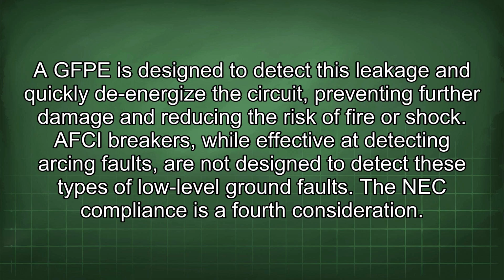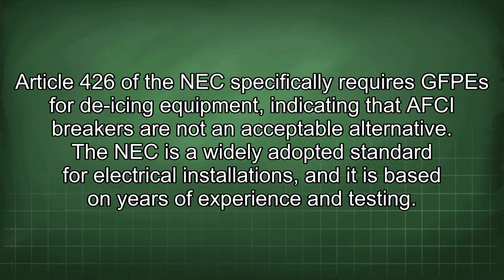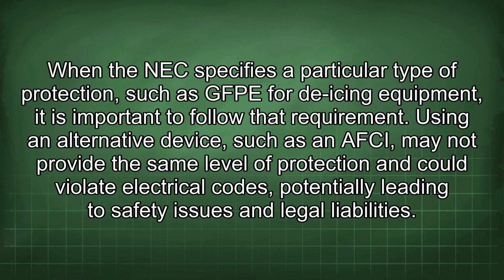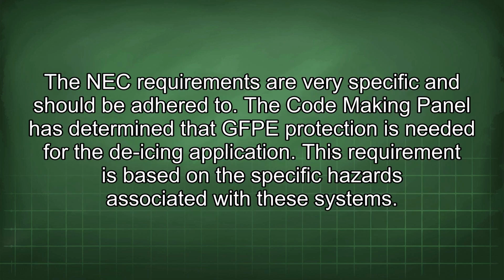NEC compliance is a fourth consideration. Article 426 of the NEC specifically requires GFPEs for de-icing equipment, indicating that AFCI breakers are not an acceptable alternative. The NEC is a widely adopted standard for electrical installations, and it is based on years of experience and testing. When the NEC specifies a particular type of protection, such as GFPE for de-icing equipment, it is important to follow that requirement. Using an alternative device, such as an AFCI, may not provide the same level of protection and could violate electrical codes, potentially leading to safety issues and legal liabilities. The NEC requirements are very specific and should be adhered to.